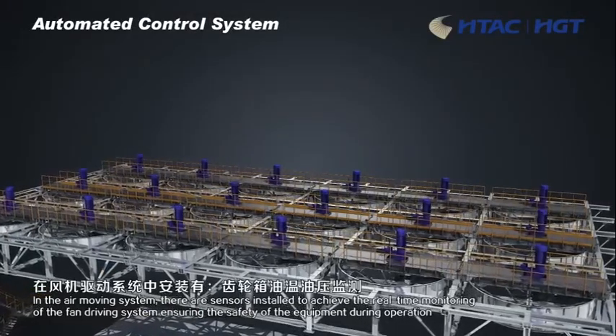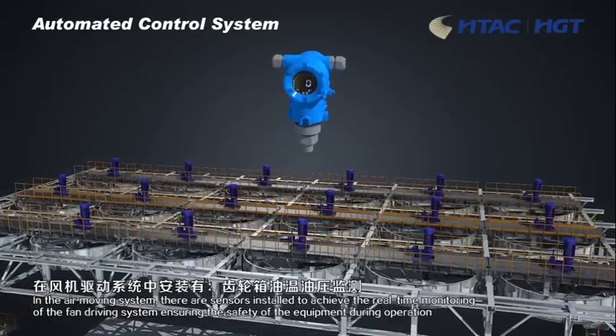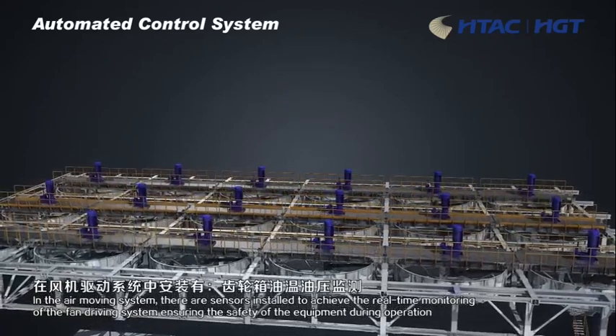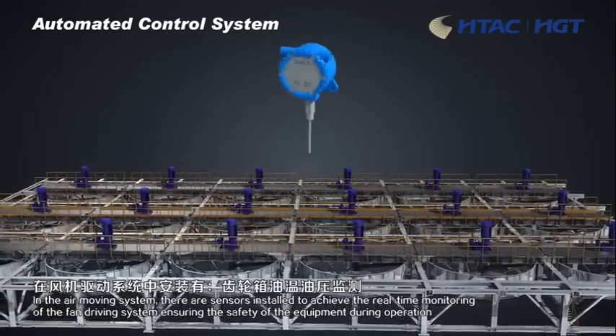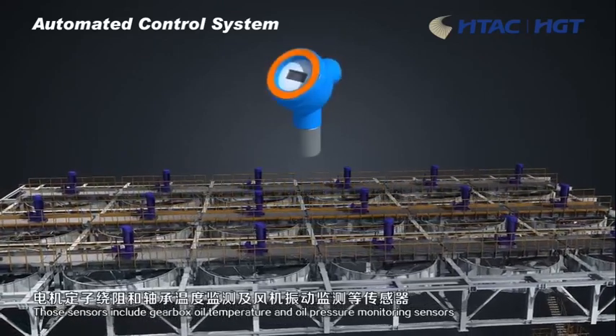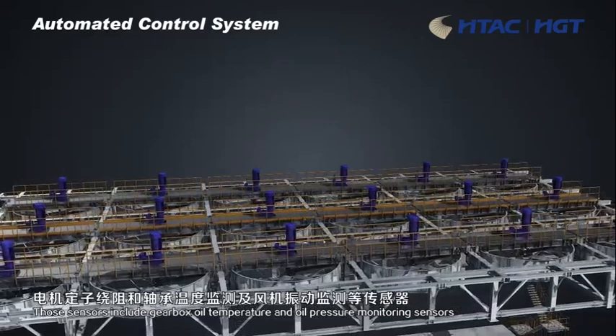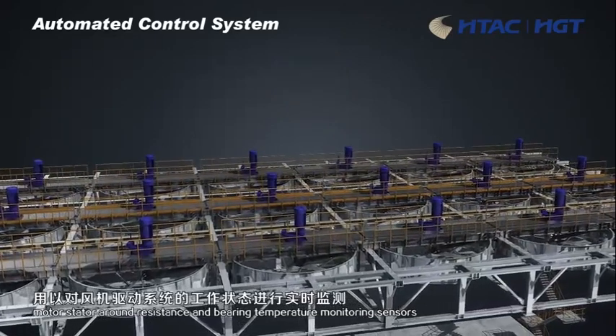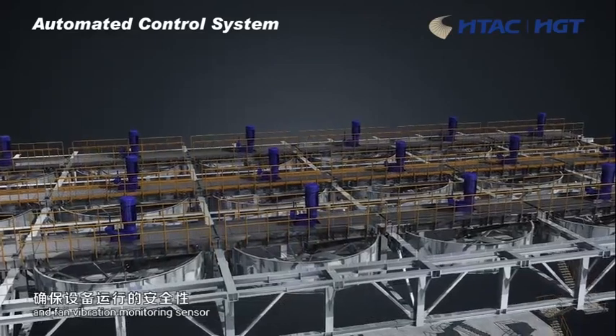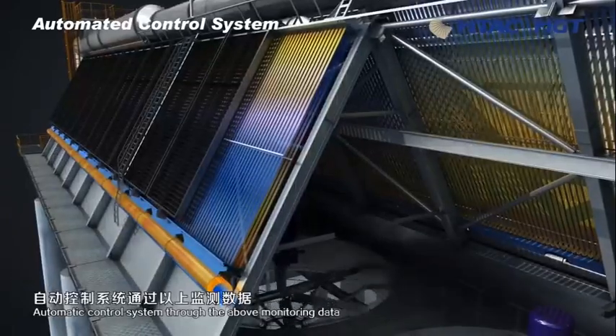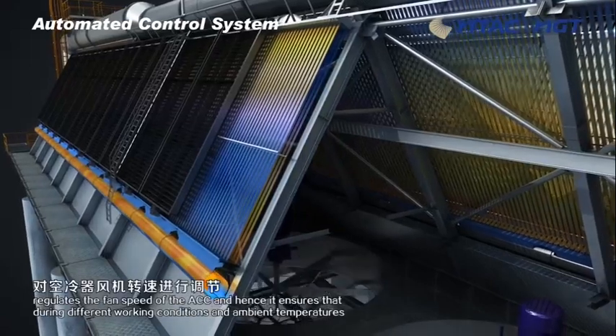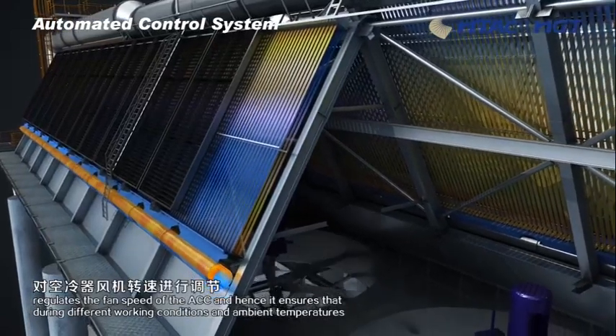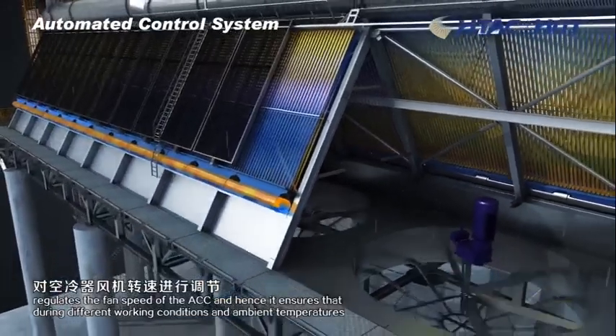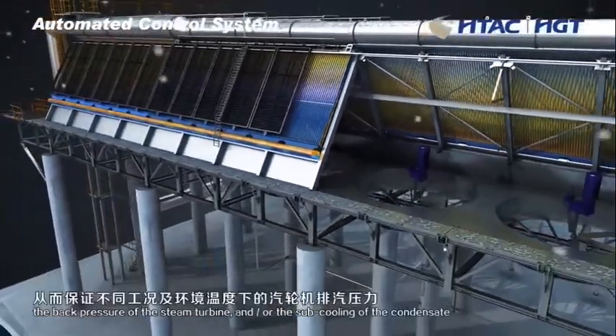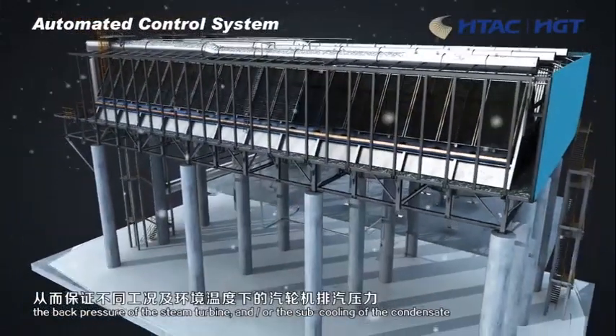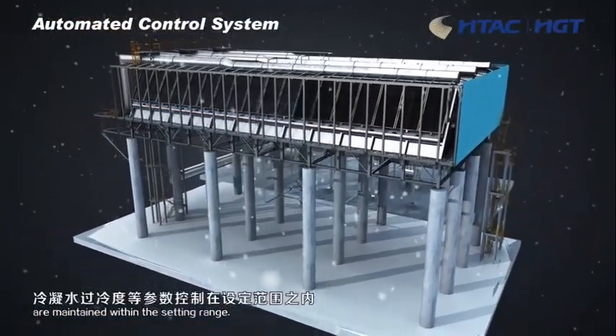In the air moving system, there are sensors installed to achieve real-time monitoring of the fan driving system, ensuring the safety of the equipment during operation. Those sensors include gearbox oil temperature and oil pressure monitoring sensors, motor stator winding resistance and bearing temperature monitoring sensors, and fan vibration monitoring sensor. Automatic control system through the above monitoring data regulates the fan speed of the ACC, and hence it ensures that during different working conditions and ambient temperatures, the back pressure of the steam turbine and/or the subcooling of the condensate are maintained within the setting range.